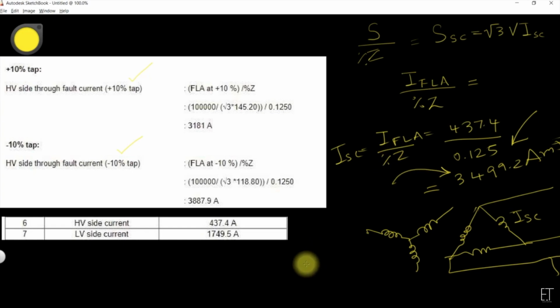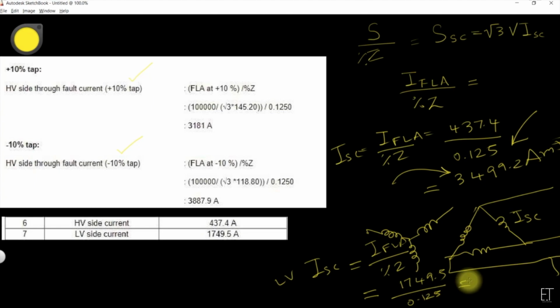So for the low voltage side, I short circuit low voltage is equal to I full load amperes divided by the percentage impedance, which is 1749.5 divided by 0.125, and that is equal to 13,996 amperes. So this is one methodology.